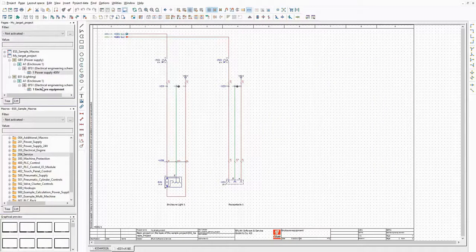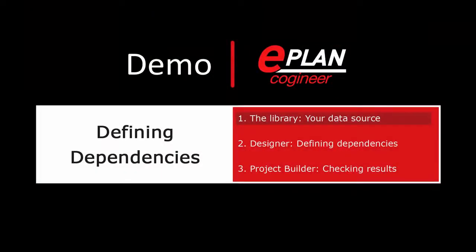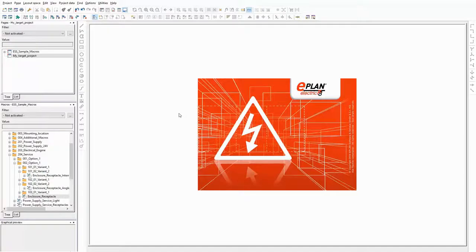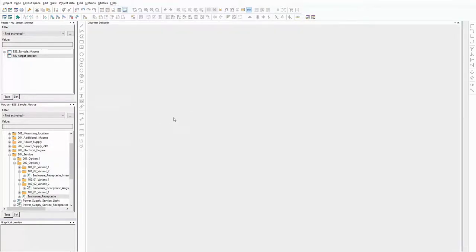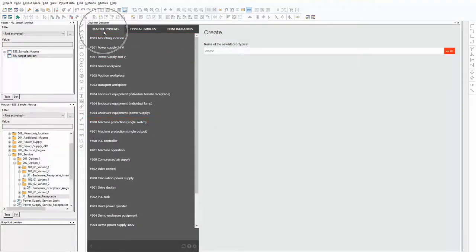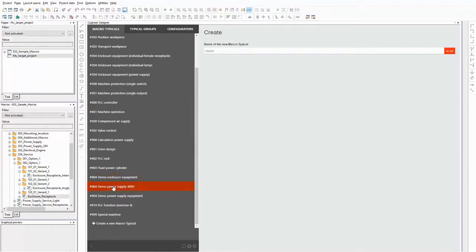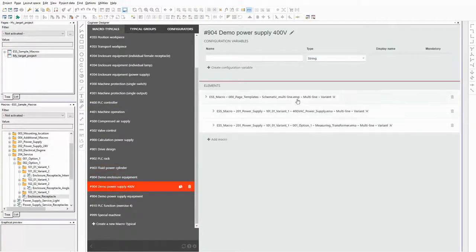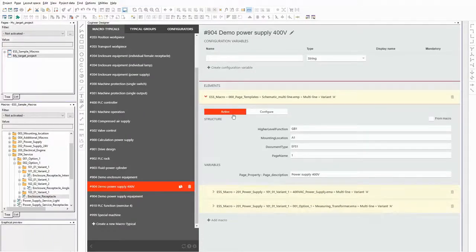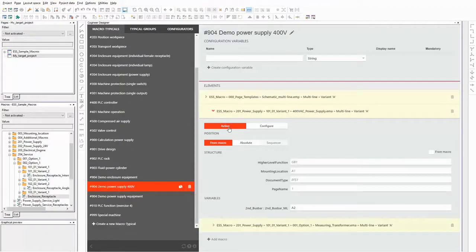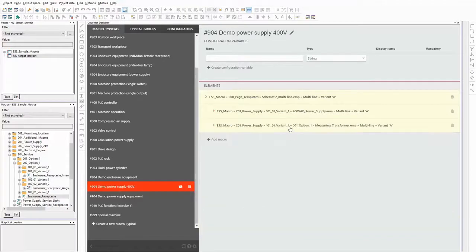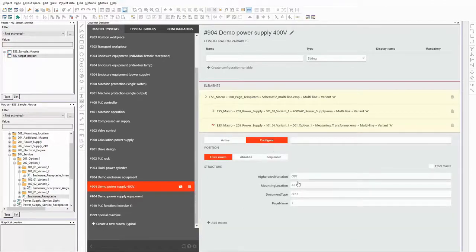Now let's have a look at the designer of EPLAN Cogineer. In this part of the video I will demonstrate how to define dependencies in the designer. I have prepared three macro typicals and added all the macros that I showed a minute ago. This one contains all macros related to the power supply. Because I want to focus on how to define dependencies, I already entered all structure information in the macro typicals. The page template and the basic power supply are set to always active. The measuring transducer should be optional, that's why I set it to configure.